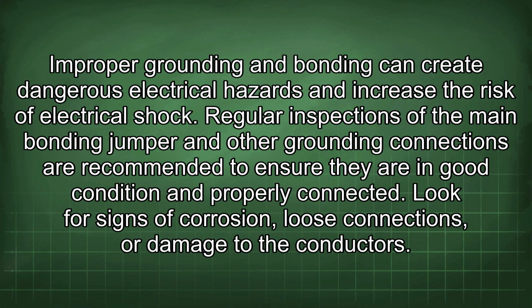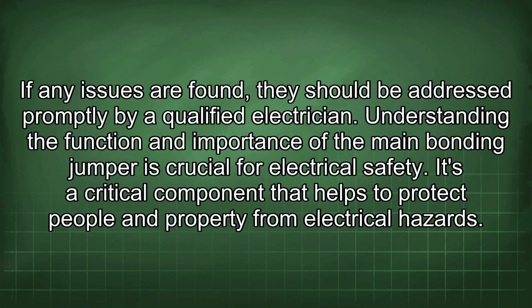Improper grounding and bonding can create dangerous electrical hazards and increase the risk of electrical shock. Regular inspections of the main bonding jumper and other grounding connections are recommended to ensure they are in good condition and properly connected. Look for signs of corrosion, loose connections, or damage to the conductors. If any issues are found, they should be addressed promptly by a qualified electrician.